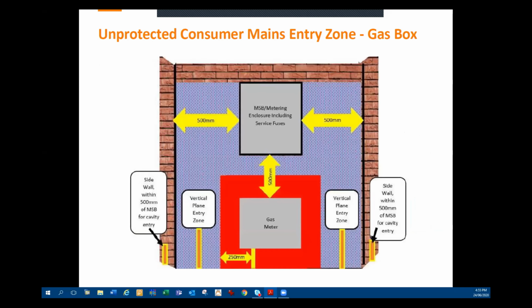In regards to the unprotected consumer mains entry zone, when there's a gas box, we've tried to re-clarify some of the issues that come around with that, which have also been introduced with the gas requirements. So basically there's a 500 clearance between the gas box and a main switchboard with metering, which includes service fuses.